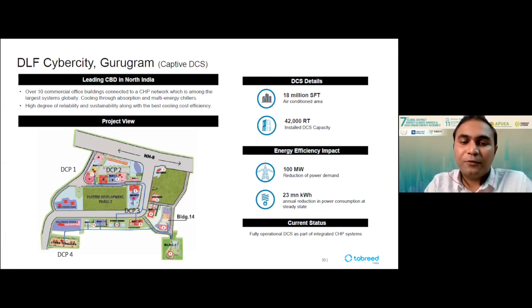They have 4 district cooling plants, as shown on the map on the left, serving around 10 commercial buildings connected to a combined heat and power plant. The base load of power is served from the CHP plant, and they have integrated absorption chillers which work on exhaust, making this a very high efficiency cooling system. They also have multi-energy chillers which can run on exhaust or other energy sources like natural gas or hot water.